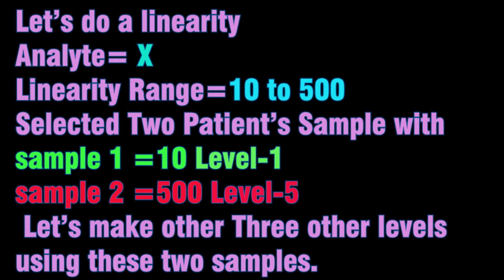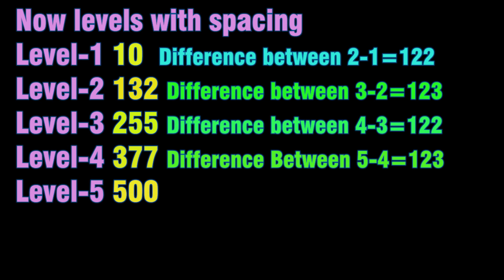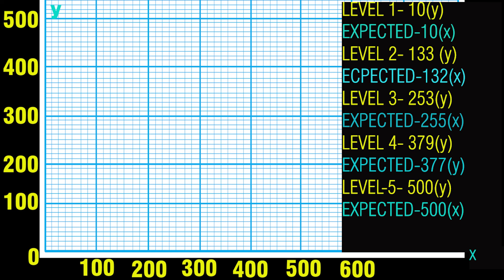Samples should be run in random order along with other samples, after checking that the instrument is calibrated and in control. After running the samples at five levels, take the mean of each sample and check for precision of the instrument. These results will be within total allowable error. Plot the sample value on the y-axis with the true value on the x-axis for visual review.